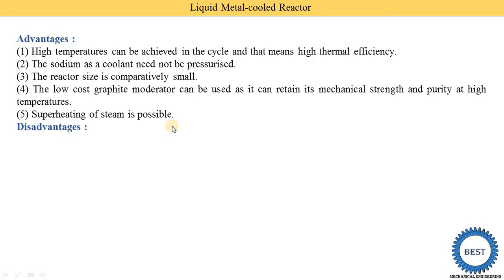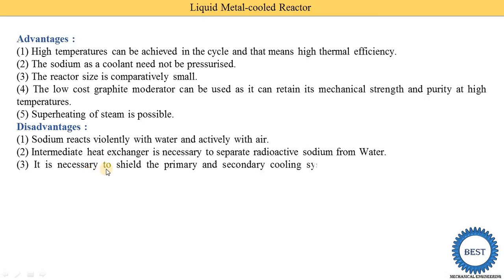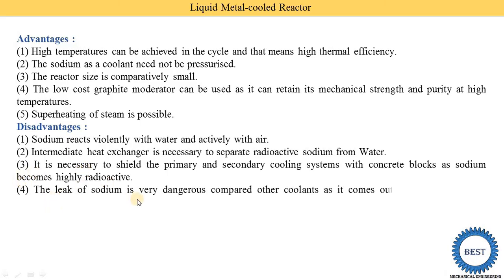The disadvantages of liquid metal cooled reactors are: first, sodium reacts violently with water and actively with air. Second, an intermediate heat exchanger is necessary to separate radioactive sodium from water. Third, it is necessary to shield both the primary and secondary cooling systems with concrete shielding because sodium becomes highly radioactive. The leak of sodium is very dangerous compared to other coolants, as it exits the reactor in a highly radioactive state.